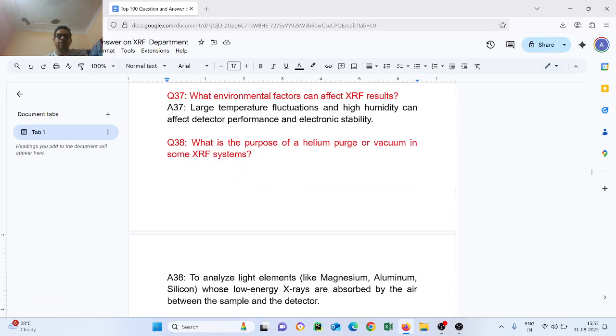Question number 37. What environmental factors can affect the XRF result? Large temperature fluctuations and high humidity can affect the detector performance and electronic stability. What is the purpose of helium purge or vacuum in some XRF systems? To analyze light elements like magnesium, aluminum, silicon, whose low energy X-rays are absorbed by the air between the sample and the detector.